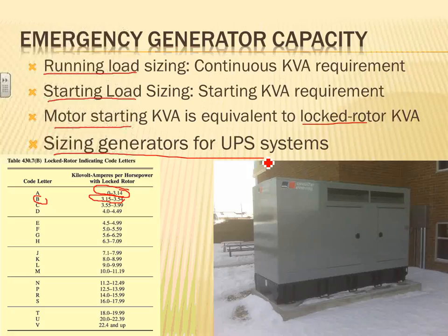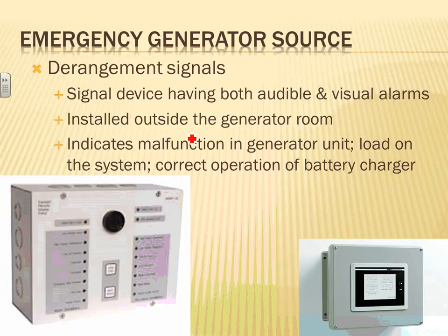Okay, 1.5. So when you have a UPS system, you have to be a little bit more conservative. If you have a 100 kVA UPS system, do you need a 100 kVA generator or do you need a 150 kVA generator? Typically, that's when you talk to the manufacturer of the UPS, so you go by 50% more. Okay, so that's the sizing.